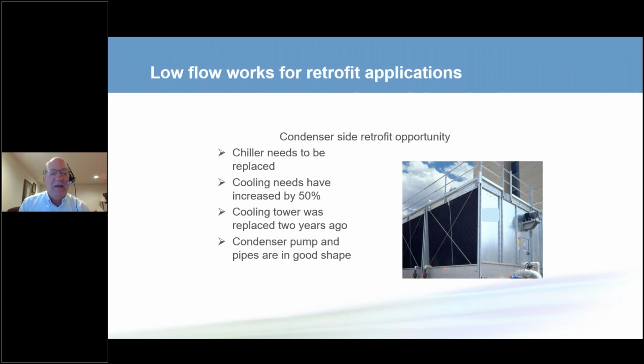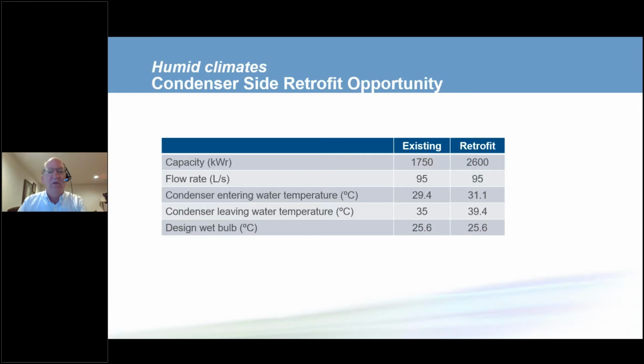And the condenser water pump and pipe are in good condition. And sometimes the pipe runs under a parking lot or something like that. They don't want to dig it up. But the first thought is we have to replace everything. We have to replace the chiller, the pipes, the pumps, the cooling towers, and the job becomes expensive and it goes out of budget. Well, we don't have to do that.